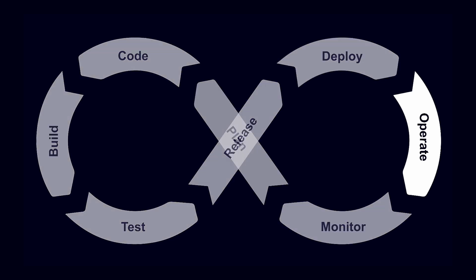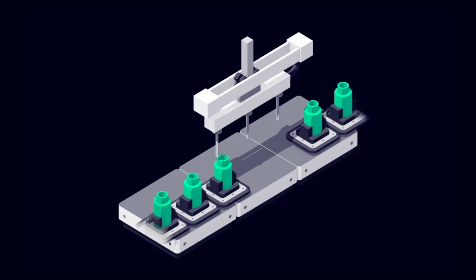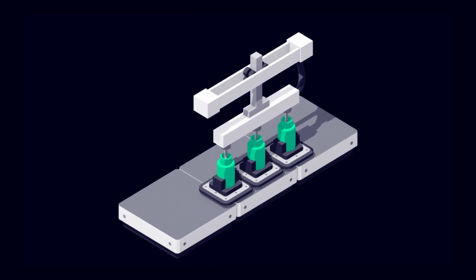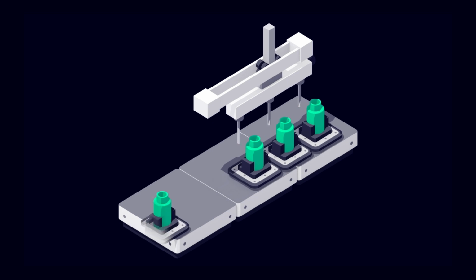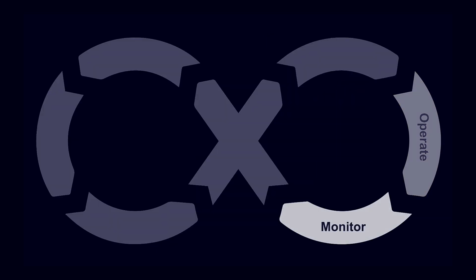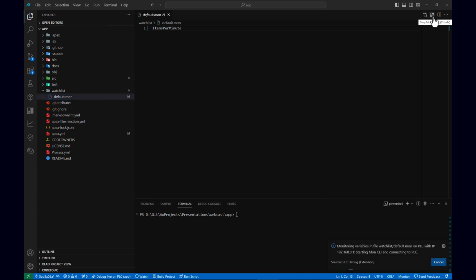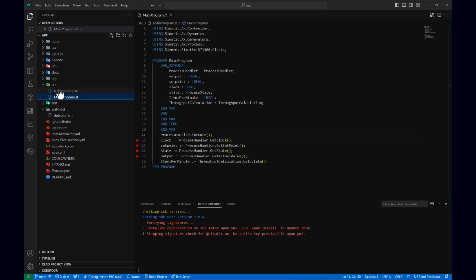For this, we will start at the operating phase. This little animation symbolizes the machine running. As you can see, it waits longer than needed in the bottom position. Let's investigate what causes this long waiting position. We do this through our monitoring and tracing capabilities with the current output to see if there is an optimization potential. For that, we can see a number, and later on we want to increase that number, which means higher efficiency. Let's do some live debugging on the program.